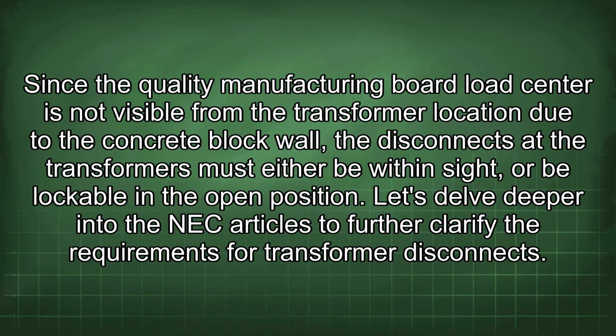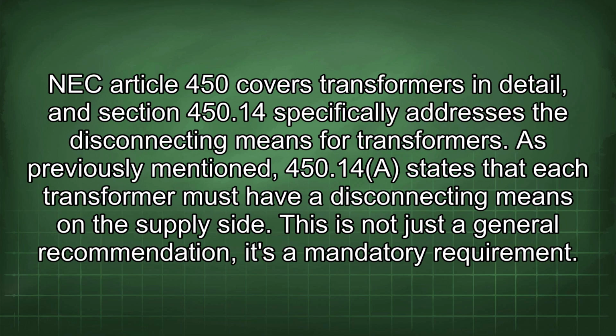Let's delve deeper into the NEC articles to further clarify the requirements for transformer disconnects. NEC Article 450 covers transformers in detail, and Section 450.14 specifically addresses the disconnecting means for transformers. As previously mentioned, 450.14 states that each transformer must have a disconnecting means on the supply side. This is not just a general recommendation, it's a mandatory requirement.